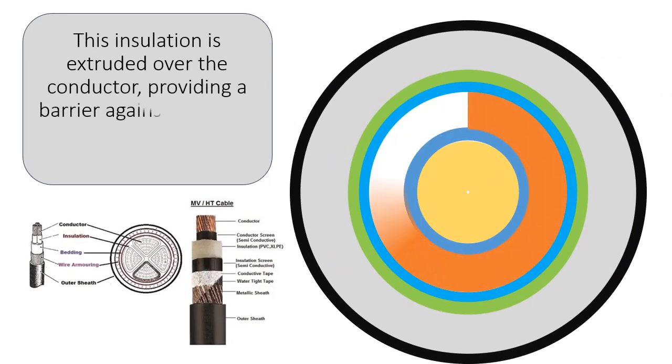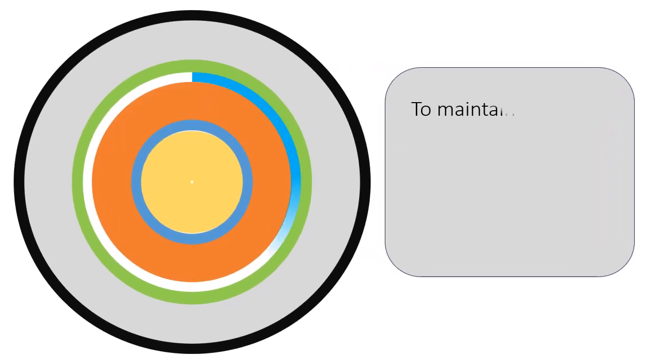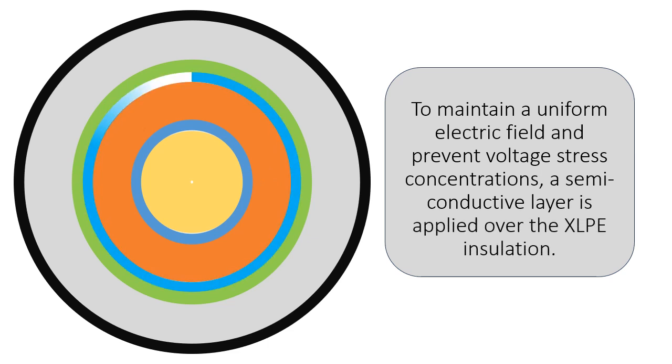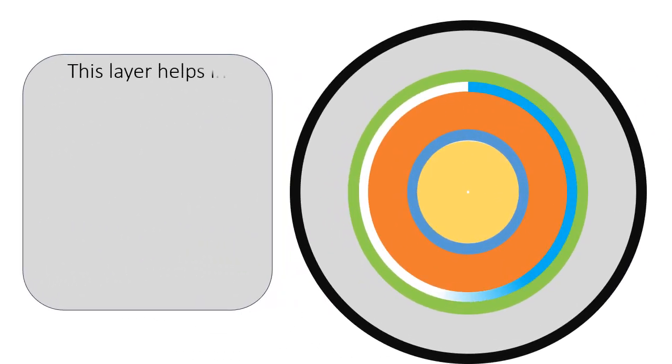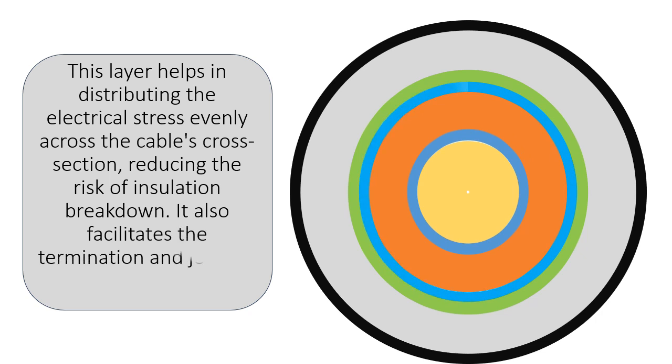Semi-conductive layer: To maintain a uniform electric field and prevent voltage stress concentrations, a semi-conductive layer is applied over the XLPE insulation. This layer helps in distributing the electrical stress evenly across the cable's cross-section, reducing the risk of insulation breakdown. It also facilitates the termination and jointing of XLPE cables.